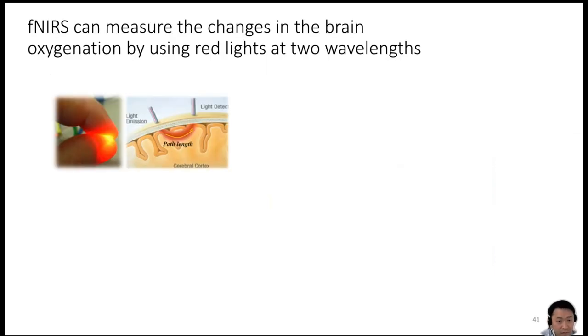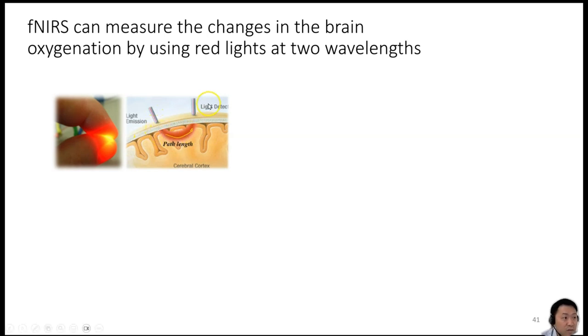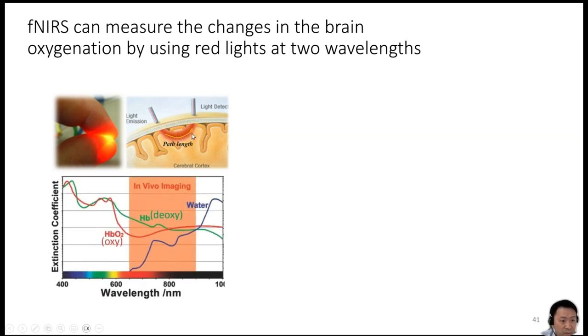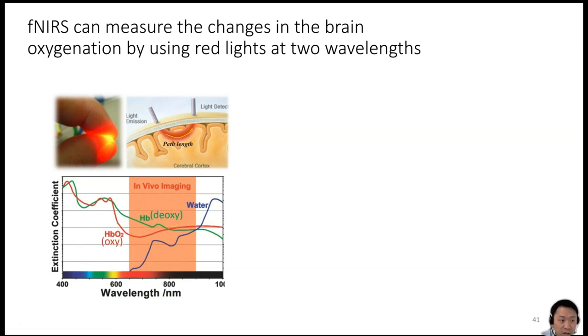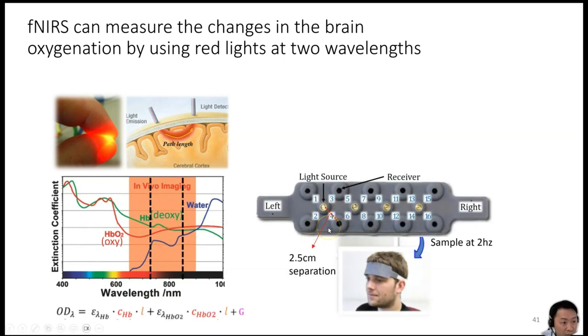Let's go over the principle of fNIRS, which measures changes in brain oxygenation using red light at two wavelengths. Our body tissue and bones are relatively transparent to red light. Light is beamed through the forehead and received on the other side; we measure the intensity of that light. Changes in intensity depend on how much light is absorbed by the hemoglobin content or red blood cells in the bloodstream. Different wavelengths are absorbed differently by hemoglobin depending on whether it is carrying oxygen — that is, oxy versus deoxy — so by using at least two wavelengths, we can resolve changes in oxy and deoxy hemoglobin as a function of time, which correlates with brain activity.